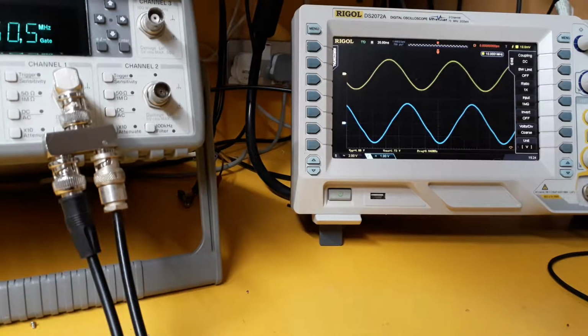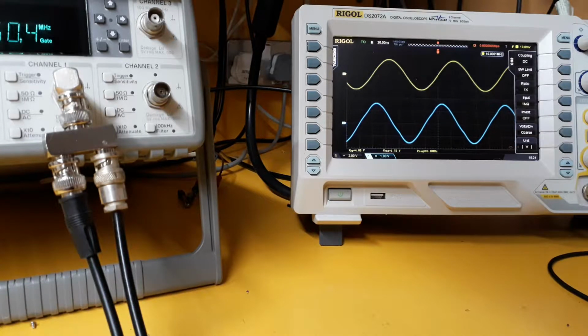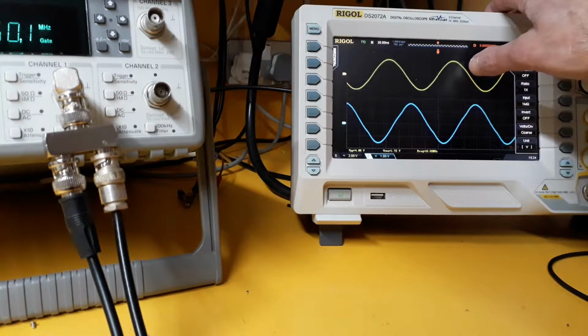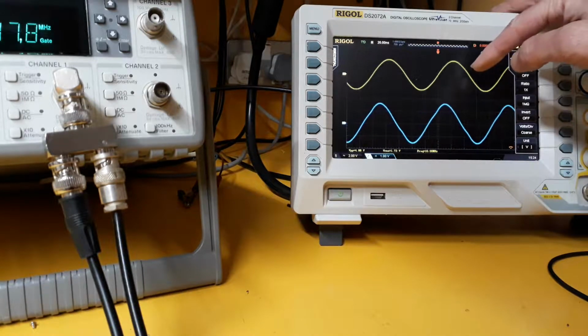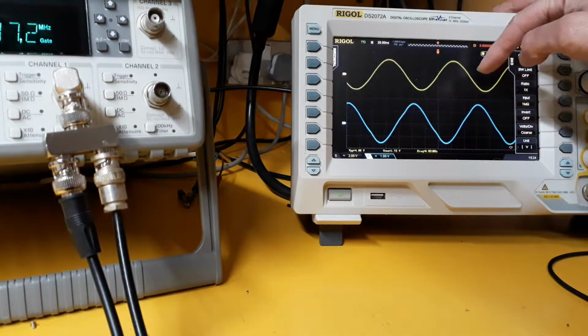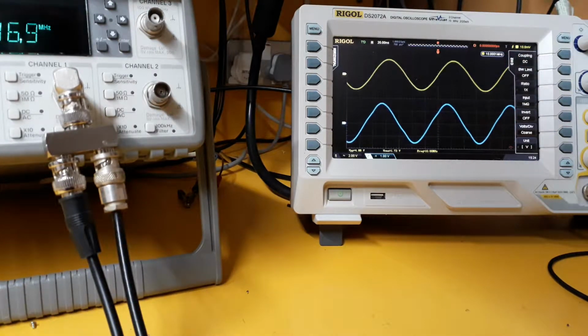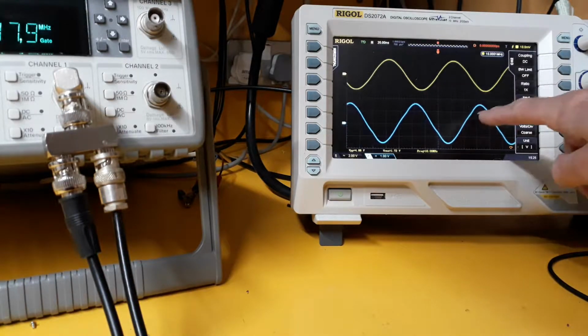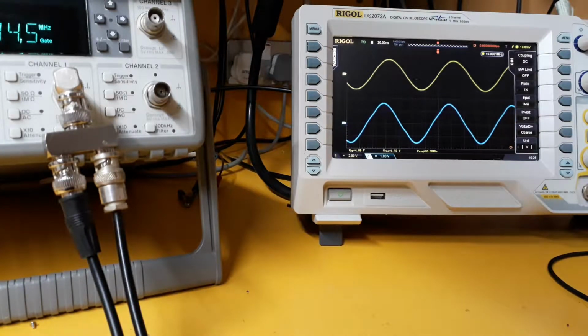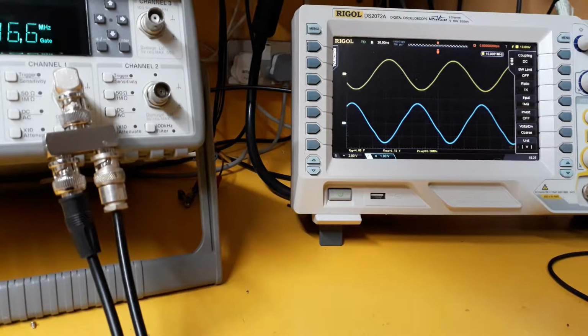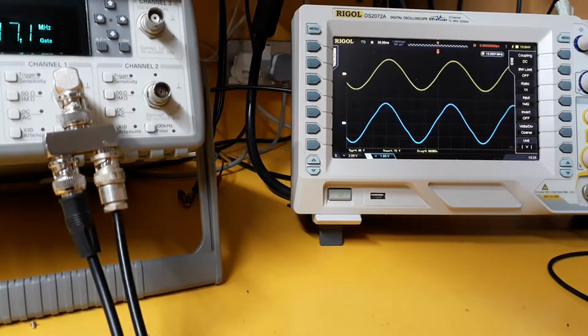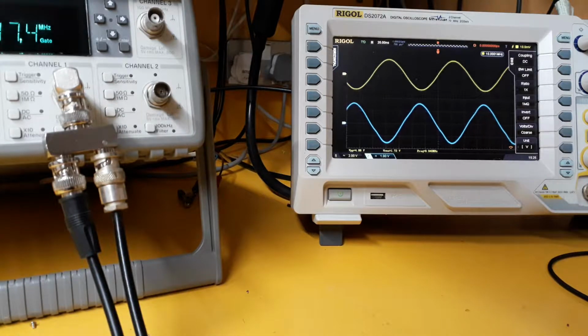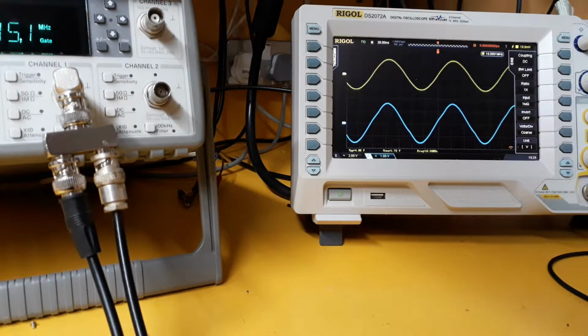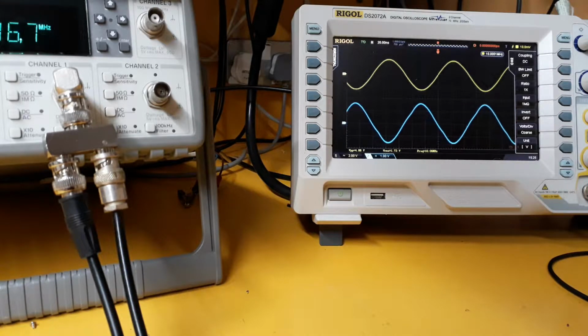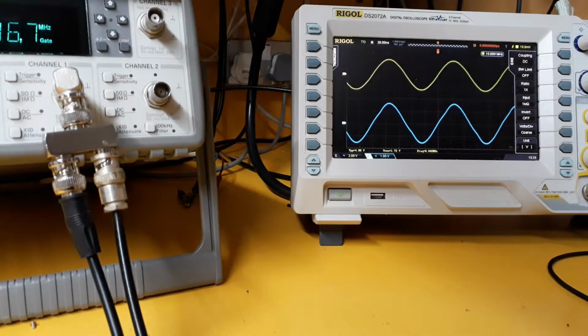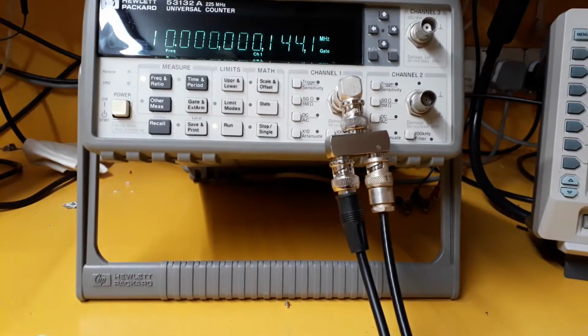Okay, I've got it wired up, ready for calibration, and I've got the scope in view. What I'm doing is putting 10 megahertz into the counter, and that's being teed off and monitored on channel 1 of the scope. And the scope's triggered on that channel, obviously. And on the second channel of the scope, I'm taking the 10 megahertz reference out from the back of the counter, which is basically what's coming out of the oven oscillator. So, as you can see, it's drifting, which is what you expect, unless the two signals are identical. And I guess the difference is, as it says on the front of the counter, 0.1 hertz.